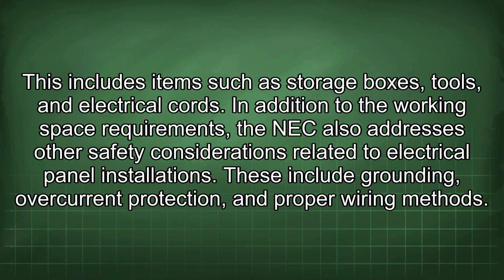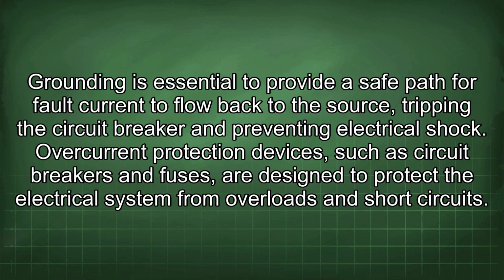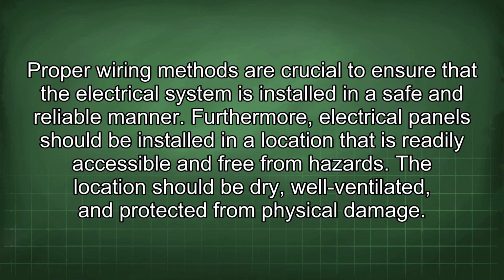In addition to the working space requirements, the NEC also addresses other safety considerations related to electrical panel installations. These include grounding, overcurrent protection, and proper wiring methods. Grounding is essential to provide a safe path for fault current to flow back to the source, tripping the circuit breaker and preventing electrical shock. Overcurrent protection devices, such as circuit breakers and fuses, are designed to protect the electrical system from overloads and short circuits. Proper wiring methods are crucial to ensure that the electrical system is installed in a safe and reliable manner.